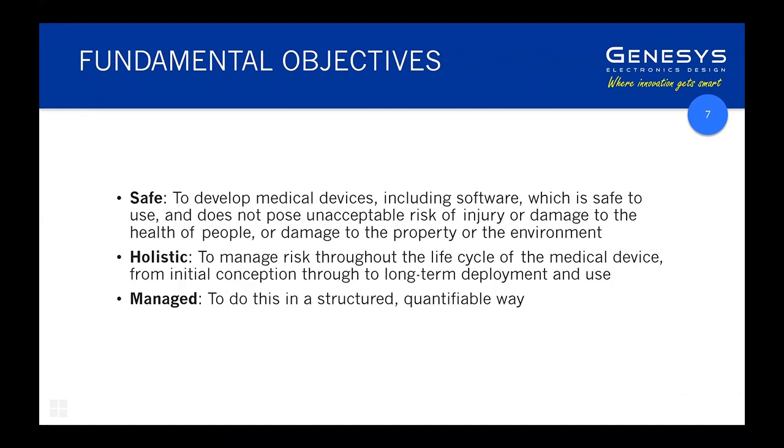So looping back on the fundamental objectives of undertaking risk management in medical device development and deployment: to develop devices that are safe for use. The dot point there actually quotes from one of the standards, but effectively, to not pose unacceptable risk of injury or damage to the health of people, in particular patients and users, but also damage to property or environment.